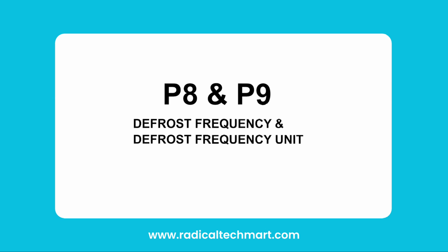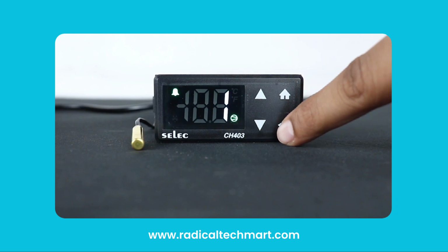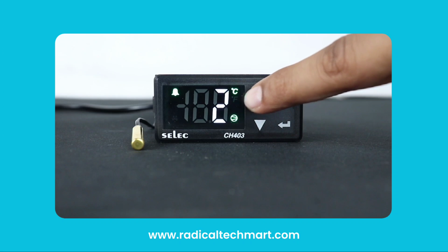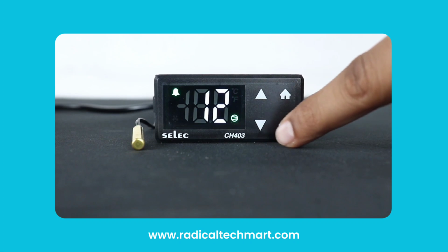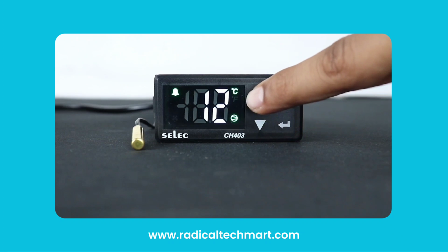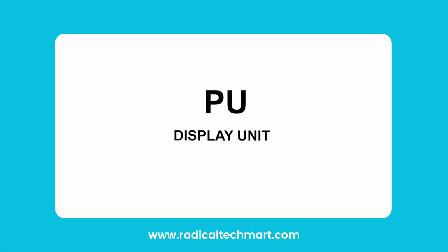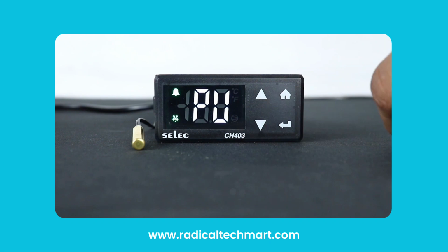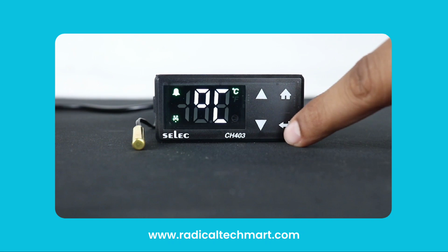Now, the next two levels, P8 and P9, are used to mark the frequency of defrosting in time ranges of hours, minutes, or seconds respectively. As per the setting done in the unit, the output relay will turn off for 5 minutes after every 12 hours continuously. Going further, we have parameter PU, which helps to change the temperature unit from degrees Celsius or degrees Fahrenheit.